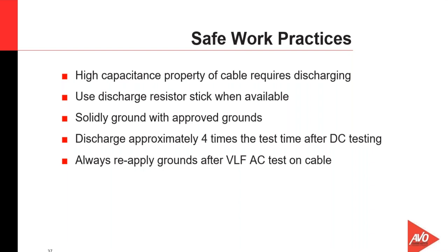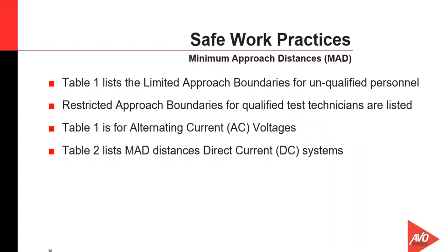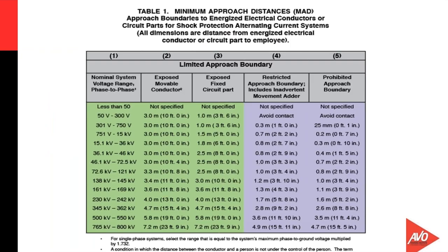Other safe practices involve the minimum approach distances. We have high voltage testing being done, AC and DC, so we're going to have these types of equipment energized with exposed live parts in the test area itself. So we do have to abide by the approach distances actually in the test area. The limited approach boundary is listed here for alternating current. If you look at columns 1, 2, and 3 on the left side, this is basically the voltage level and the approach distances to movable and fixed parts for unqualified persons.